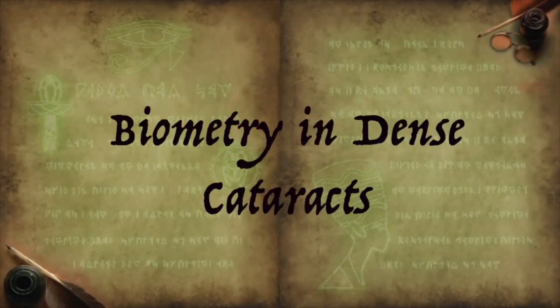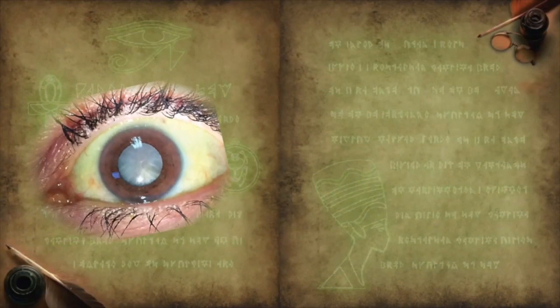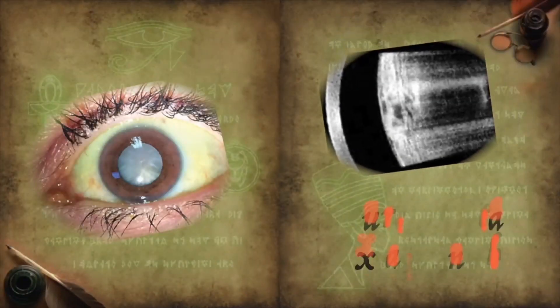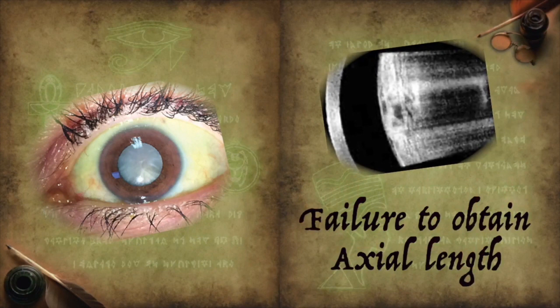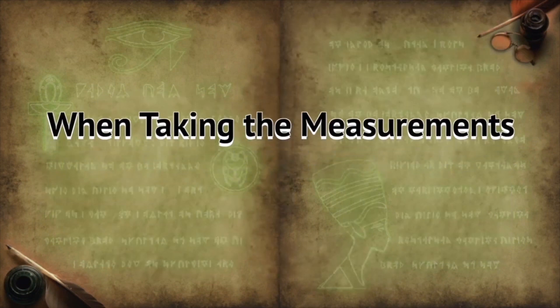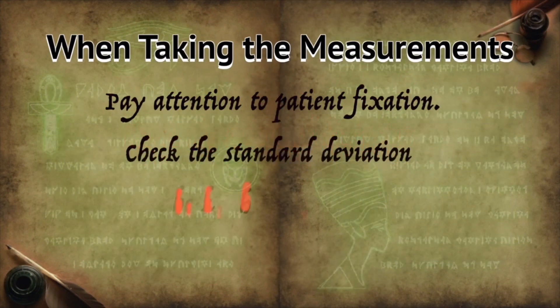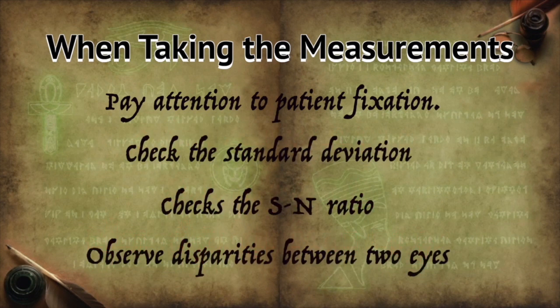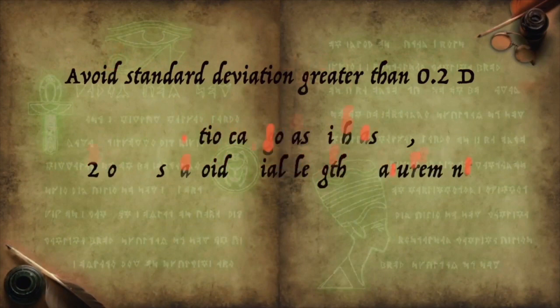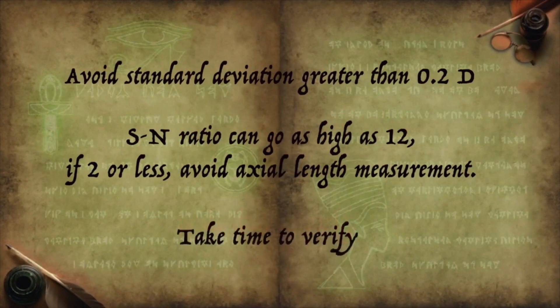Biometry in dense cataract is another tricky situation. In dense cataracts, we fail to obtain the axial length using conventional devices. This is when we have to go back to ultrasound and choose the dense cataract mode in LENSTAR or the new IOL Master 700. The commandments here are to check the standard deviation and the signal-to-noise ratio between both eyes. Standard deviation more than 0.2 diopters should be avoided, and avoid a signal-to-noise ratio less than 2.